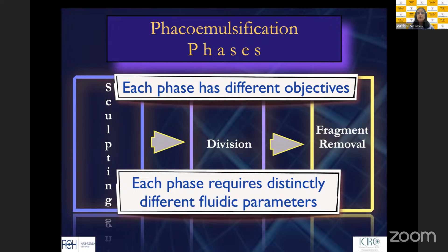So why do we need to divide this in our mind? Typically, when I learned phaco, there was only one box on my machine: there was a pre-phaco and there was a phaco. So in that phaco, everything was done. Then I realized that in sculpting, I want to reduce my vacuum because I don't want to, by chance, pull anything while I'm making that trench. So I reduce my vacuum, I reduce my flow rate, and I have good energy, ultrasound. When I'm dividing, like I said, I want good energy so that I can enter that lens material, and then good vacuum to hold it so that I can chop it.